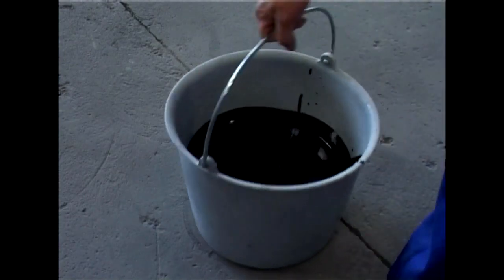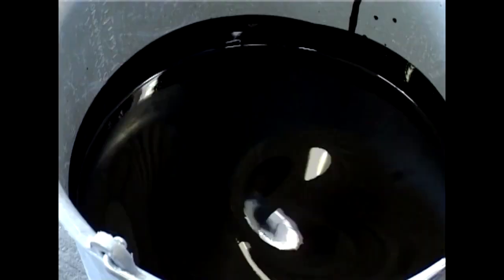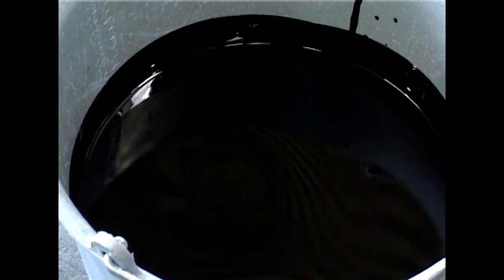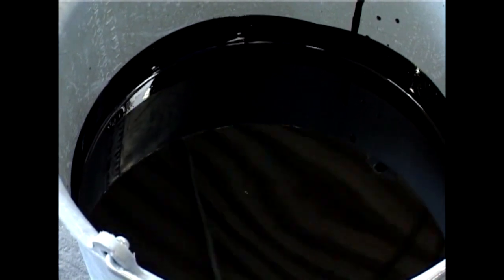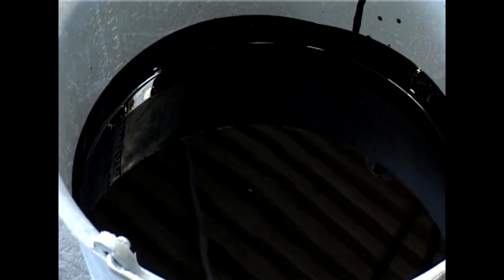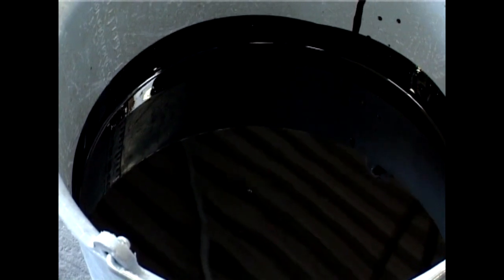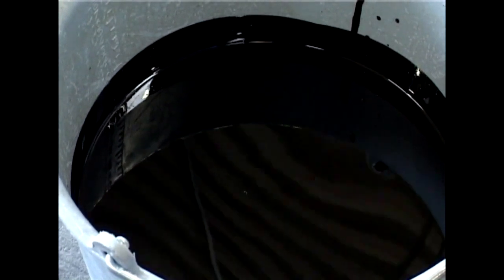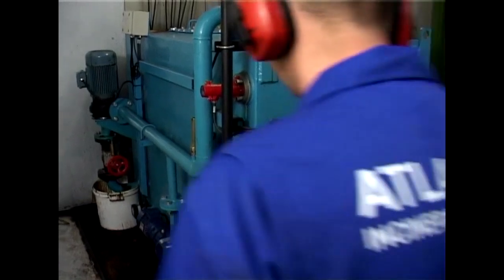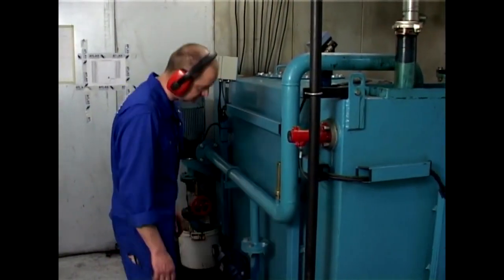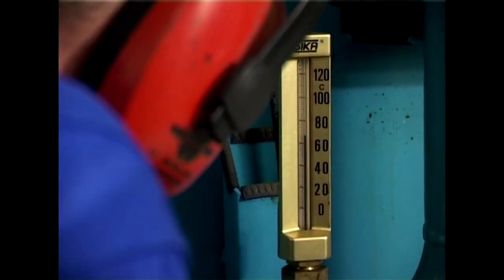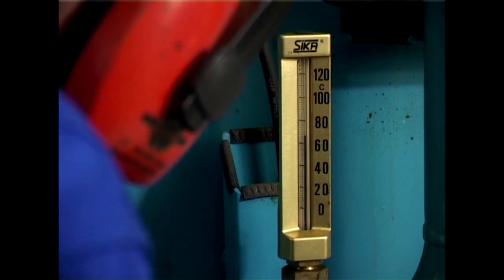Since oil sludge mainly contains remains of the heavy fuel oil, it's necessary to heat it up before trying to burn it. It is a good idea to heat up the sludge oil to around 60 to 70 degrees Celsius before trying to incinerate it. You can read the temperature on the thermometer installed on the tank.